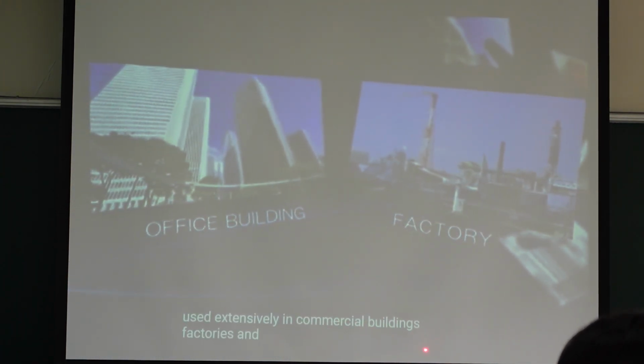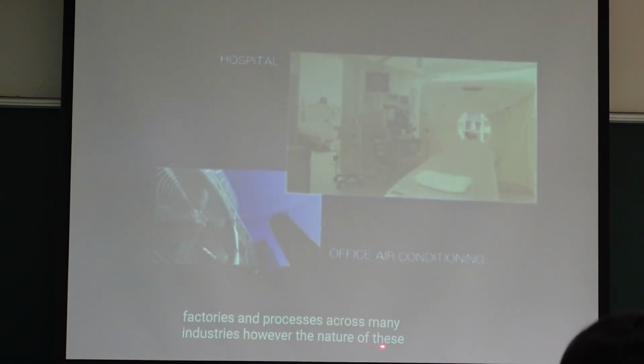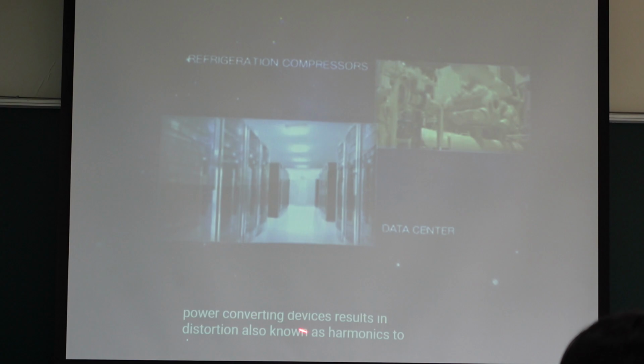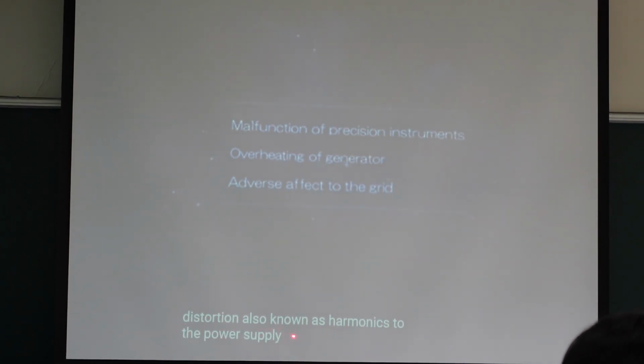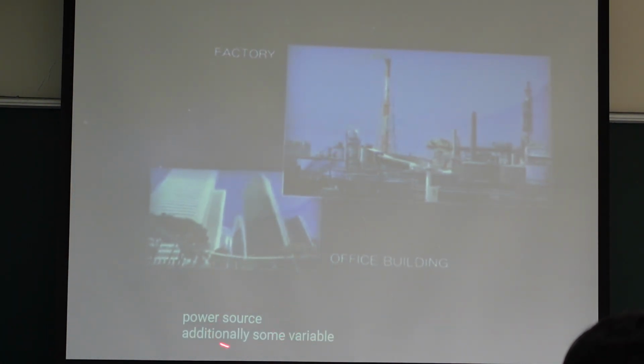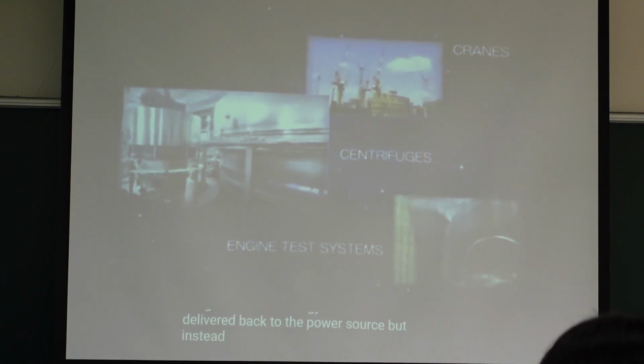Electronic variable speed drives benefit our lives in many positive ways. They are used extensively in commercial buildings, factories, and processes across many industries. However, the nature of these power converting devices results in distortion, also known as harmonics. If you use a rectifier power supply, it creates distortion. This distortion can cause problems with other applications. Energy is not delivered back to the power source, but instead often gets wasted in the form of heat.